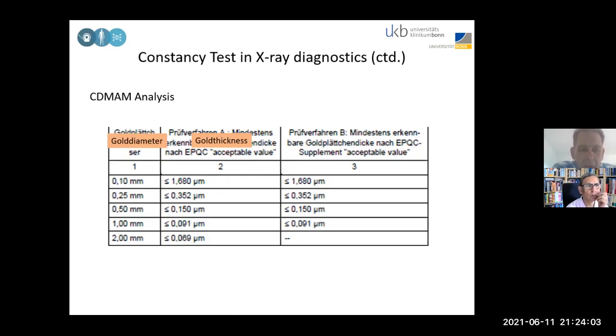These are the minimum requirements you should achieve. Actually, a gold diameter of 0.1 millimeter you should be able to recover, and a thickness smaller than 1.68 micrometers you should achieve. If you would like to do that in conventional radiography, you may fail, because this is maybe not possible if you have a lung examination, for example.